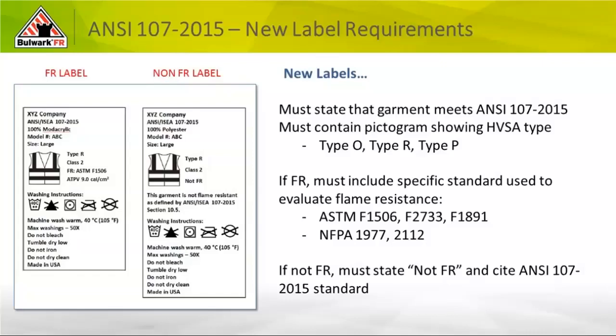These designations have to be in the label — that's the only way you can claim to be both flame-resistant and ANSI 107 compliant in the same garment. If it is not one of those five standards, the label has to tell you this is non-FR. That is extremely important because there are many substandard FR vests and rain gear in the market today that would fail miserably in an arc flash or a flash fire. If you have an arc flash or flash fire hazard and you've spent tens or hundreds of thousands of dollars on your FR clothing program, you can be putting it in extreme jeopardy by placing a non-compliant FR vest on top of one of your employees.